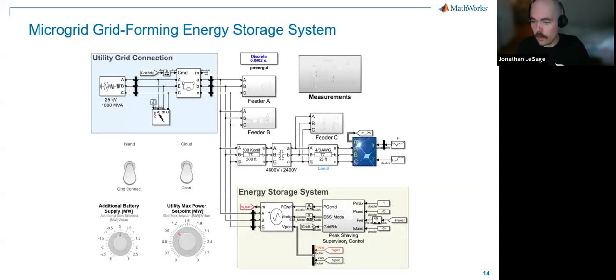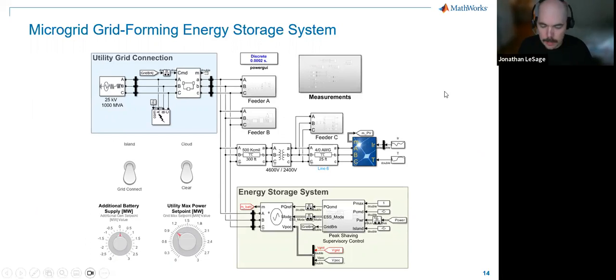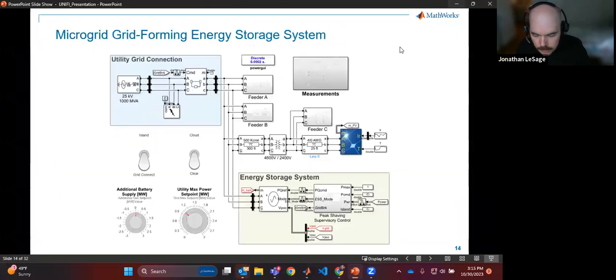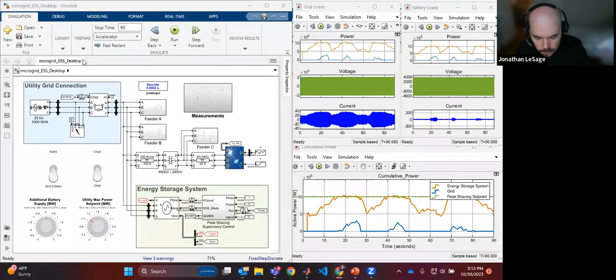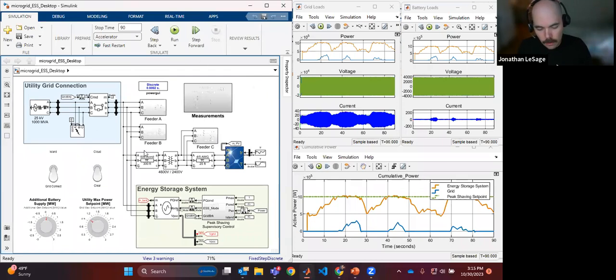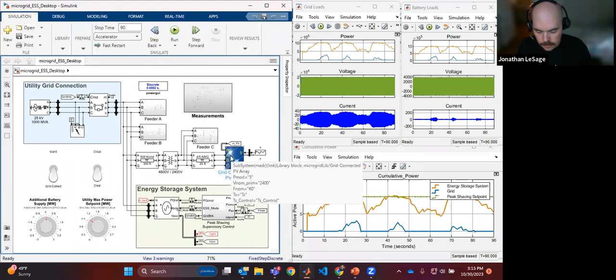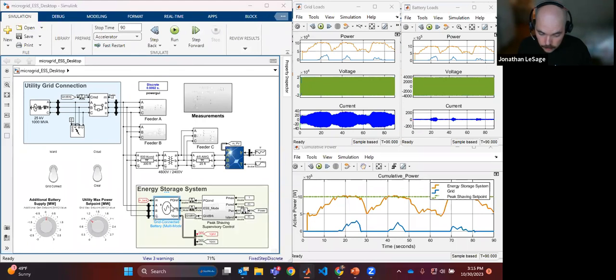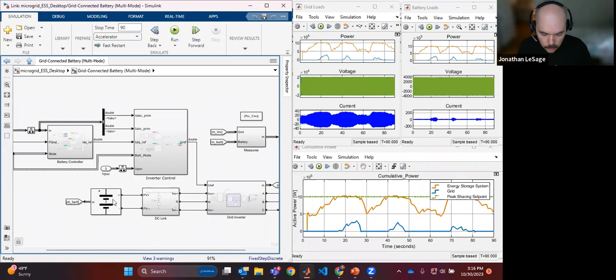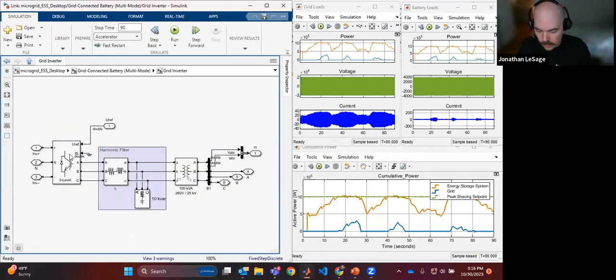I'm going to hop over to the software. This is an example model of a microgrid system. I've got different feeders — a grid-scale PV system here, and an energy storage system. Double-clicking and going under the hood, I can get into the specific chemistry — this is lithium-ion — and look at the different control strategies. Here's my inverter connecting the battery system to the grid, with layers of control tasks: voltage control, current control depending on the mode selected.